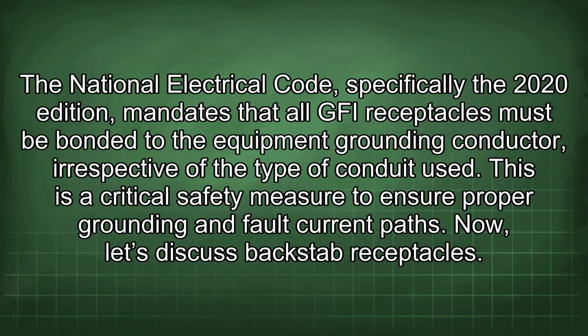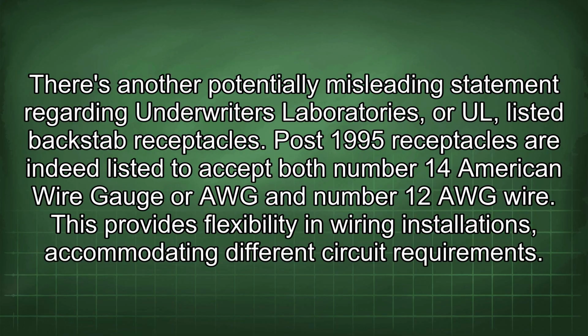Now let's discuss backstab receptacles. There's another potentially misleading statement regarding Underwriters Laboratories, or UL, listed backstab receptacles. Post-1995 receptacles are indeed listed to accept both number 14 American Wire Gauge, or AWG, and number 12 AWG wire. This provides flexibility in wiring installations, accommodating different circuit requirements.